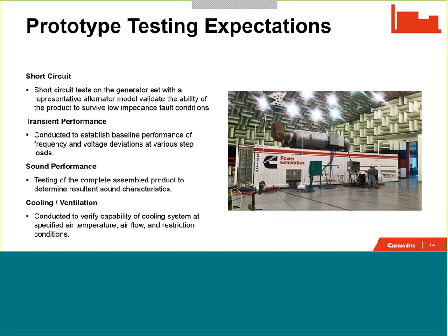The last one I'll talk about here is on the cooling and ventilation side. This is another key piece that we see drives the difference between an assembler and a manufacturer, and that's validation of the cooling system. Not only should the cooling system be validated by the generator set manufacturer for the air temperature, airflow and restriction conditions, but you'll see that some manufacturers are actually capable of testing their cooling systems at temperature. And so when you see a manufacturer who provides a cooling system that is rated for 104 degrees Fahrenheit, ask whether or not that cooling system was actually tested at 104 degrees Fahrenheit, or if it was tested at whatever temperature happened to be available in the test cell that day, and that data was extrapolated.